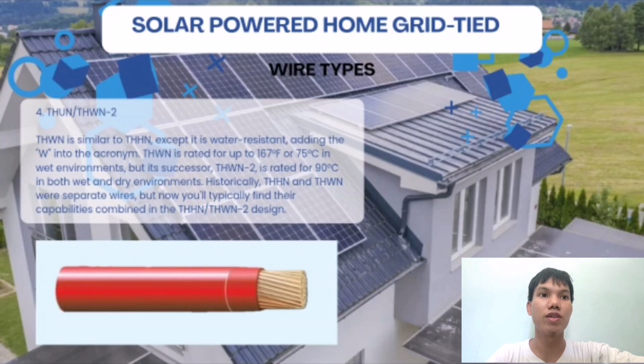In a grid-tied solar home this is crucial. Think about the outdoor conduits connecting your roof panels to the inverter. These pipes can trap rainwater or experience extreme humidity changes through the seasons. While standard wire might degrade over 5 or 10 years of wet-dry cycles, THWN2 is built to endure them for decades.